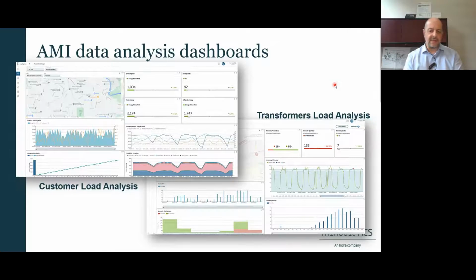Customer load analysis looks at loads at the customer level. When we aggregate that data, we start to analyze service transformers, normally ones that aren't sensorized and for which the utility has very little information. This lets us see how those transformers are being loaded, which becomes very important when analyzing new loads coming onto the network, such as electric vehicle charging.